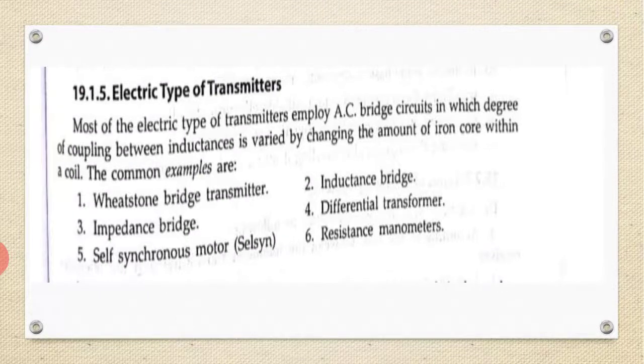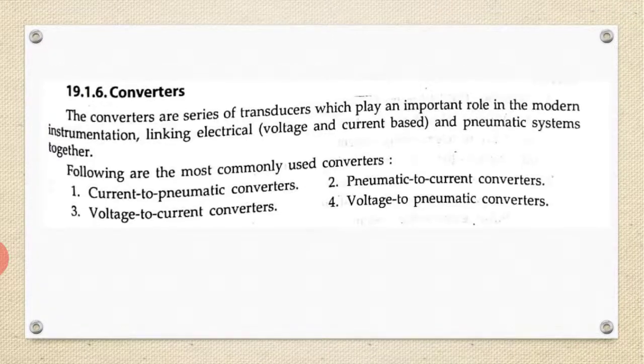For electric type transmitters, most employ AC bridge circuits in which the degree of coupling between inductances varies. The inductance is varied by changing the amount of iron core within a coil. Examples include: Wheatstone bridge transmitter, inductance bridge, impedance, differential transformer, self-synchronous motor, and resistance manometer. The most commonly used converters are current-to-pneumatic, pneumatic-to-current, voltage-to-current, and voltage-to-pneumatic converters.